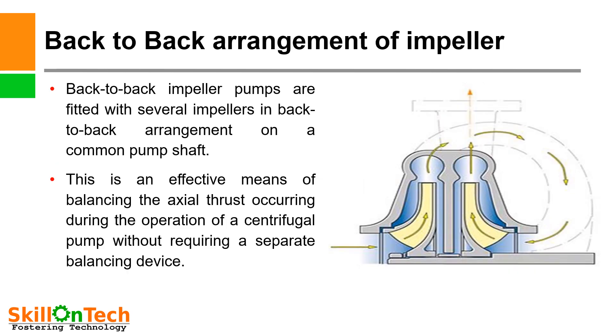Back-to-back arrangement of impellers: You can see a picture of back-to-back impeller arrangement. There are two impellers — impeller number 1 and impeller number 2 — arranged back to back. The axial thrust produced by both impellers cancels each other; one impeller discharges in one direction and the other in the opposite direction, with suction forces also nullifying each other. Back-to-back impeller pumps are fitted with several impellers in back-to-back arrangement on a common pump shaft. This is an effective means of balancing axial thrust during centrifugal pump operation without requiring a separate balancing device.